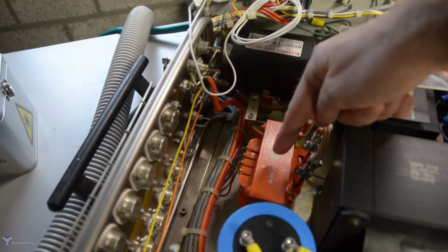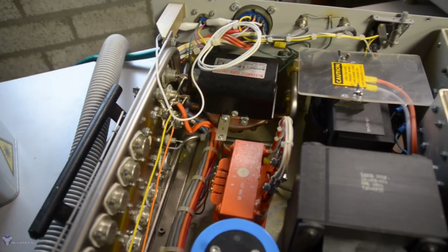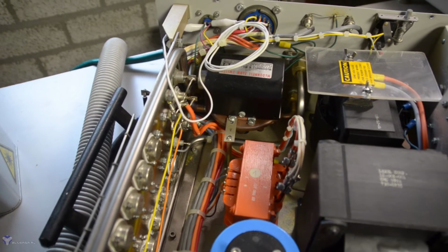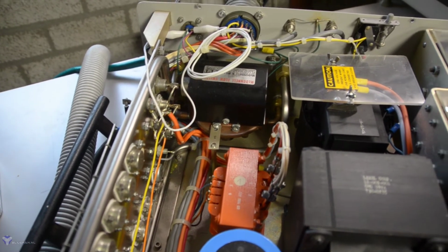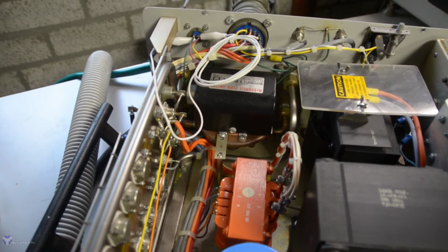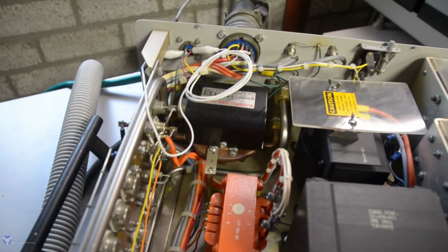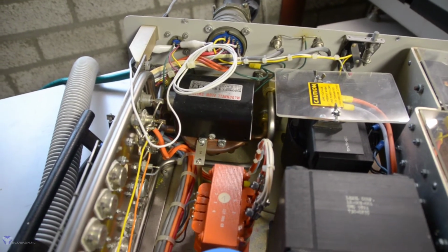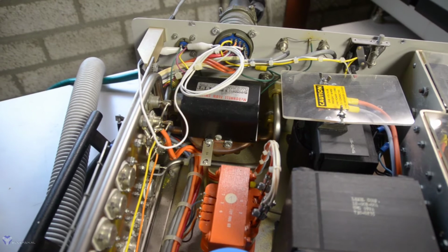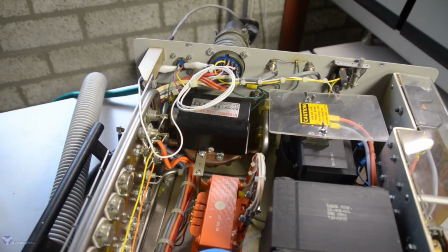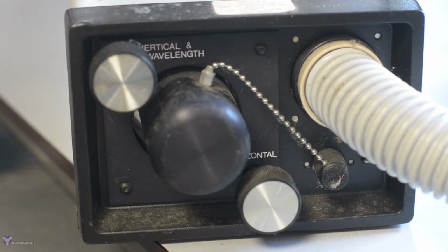And the orange transformer over here is the filament transformer. This one generates a few volts at a very high current for the filament. At the back here is the flow switch, which makes sure that the laser can only run if there is sufficient cooling water flow.